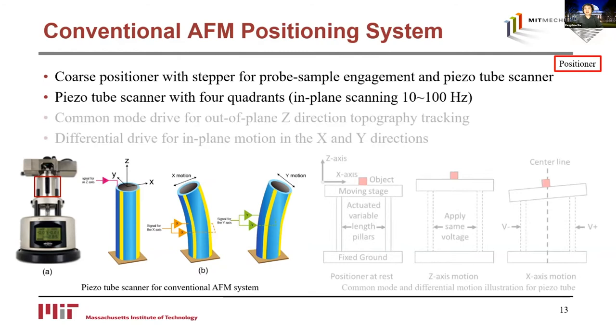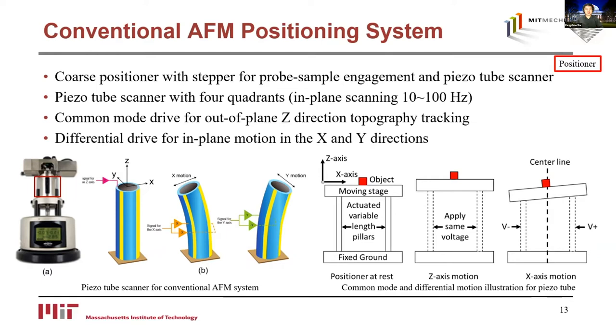Now let's look at the operational principle of a conventional AFM positioning system. A coarse positioner with a stepper motor is typically used for probe-sample engagement, and piezo tube scanners with four quadrants are used for scanning, typically below 10 lines per second. Out-of-plane z-direction motion is realized by common-mode drive — applying similar voltage to all four quadrants. When differential voltage is applied, a tilt of the sample creates in-plane motion. Since the motion is on the order of microns and the scanner dimension is on the order of centimeters, the tilt angle is very small and can be compensated easily. This design is simple and widely used, though difficult to improve bandwidth due to bulk size and coupled motion.